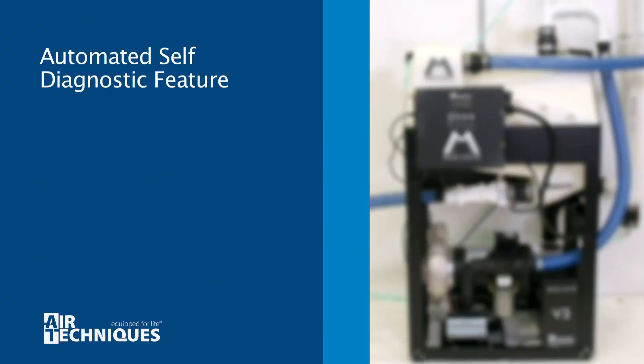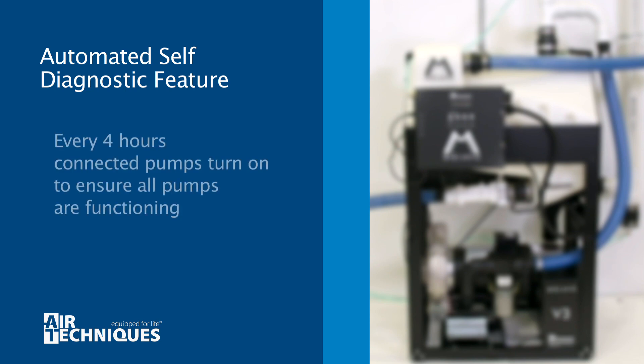The automatic self-diagnosis feature: every four hours, each pump connected to the MMC that is not on will be turned on for six seconds then turned off sequentially. This feature ensures that all pumps are functioning properly and prevents locked rotors.